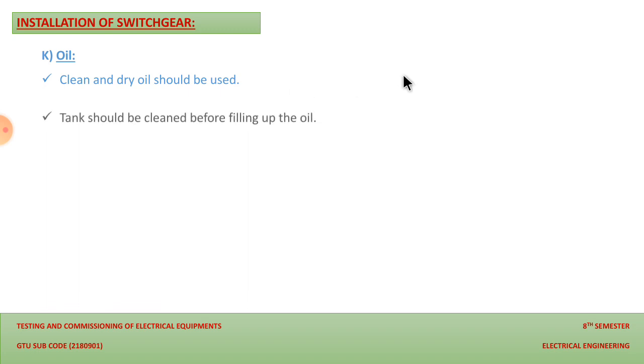Then the next point for the installation of the switchgear is oil. So again, oil is an important factor for the installation of the switchgear. So clean and dry oil should be used. It must not be contaminated. There should be no contamination inside the oil, or we can say there should be no moisture inside the oil. Dry oil means there is no contamination and no moisture inside the oil, so we should ensure that before we use that oil for the operation of the circuit breaker.